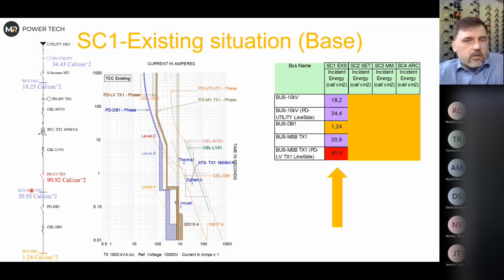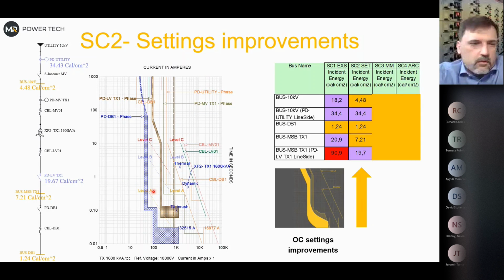We have a low voltage panel, which is 20 calories, which is quite high, and then we have a panel board, which is 1.24, which is almost on the border of the arc flash 1.2 calories level. Still, this is not very well done from a selectivity point of view, so we will improve it as well. So let's go. The first one is overcurrent settings.